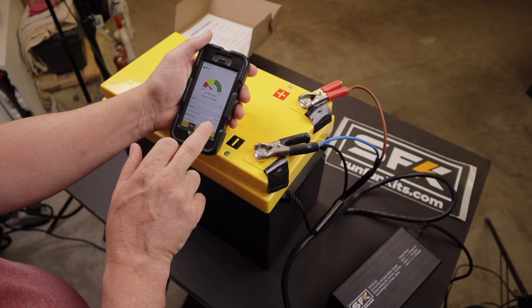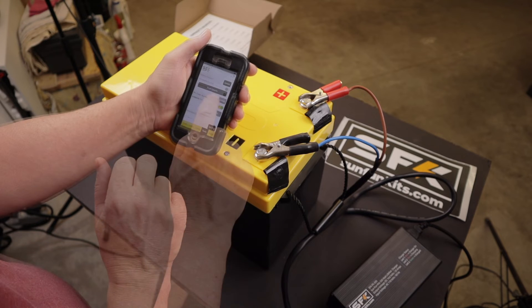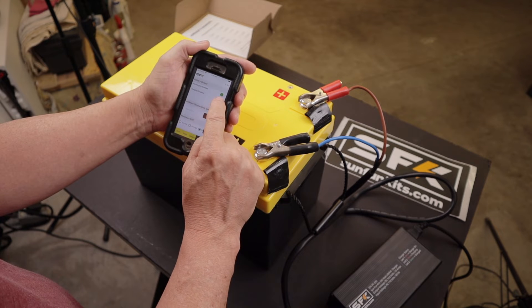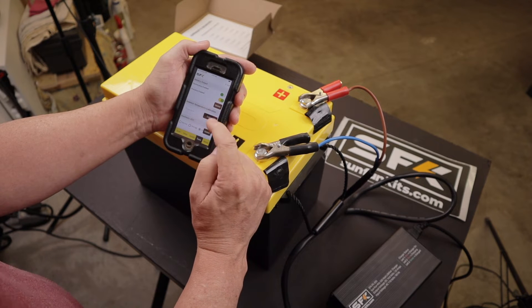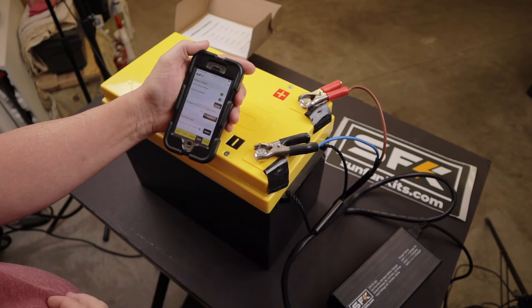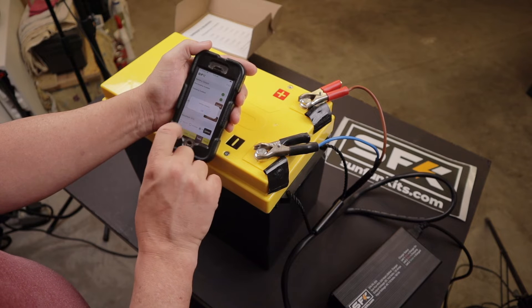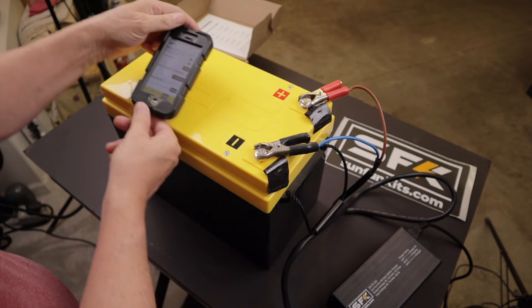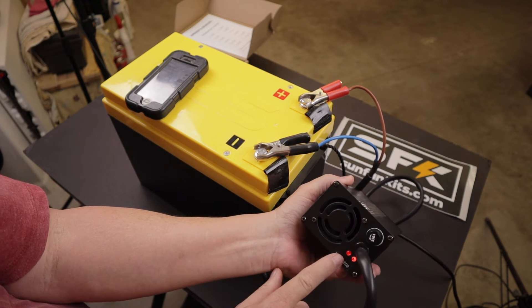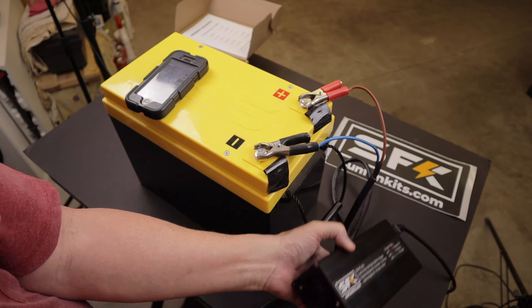It's sitting at 13.17 volts. Let's go to Tools. I have the charge disabled at the moment, so let's go ahead and set it to charge enabled and hit update. Now I heard the battery charger come on. The setting update is OK, the fan has come on, and now we have two red lights — one indicating it's on, and two indicating that it is charging.